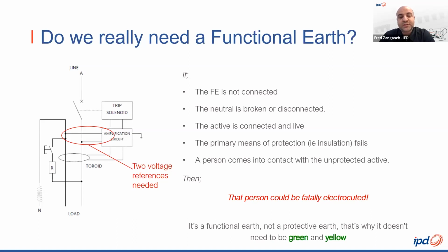If we have a situation where the functional earth is not connected, or we have a broken neutral, or it's been disconnected, the active is connected and live, and the primary means of protection such as insulation fails, this additional layer of safety with the functional earth will come in. Now, if a person comes into contact with the unprotected active, then that person could be electrocuted.